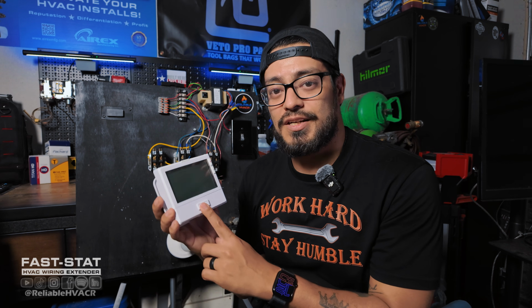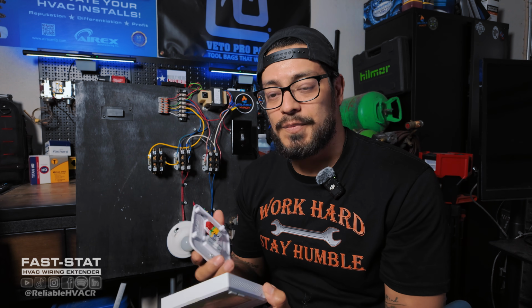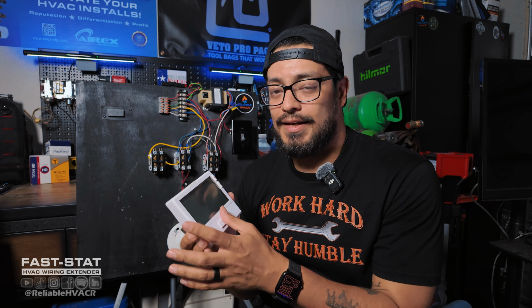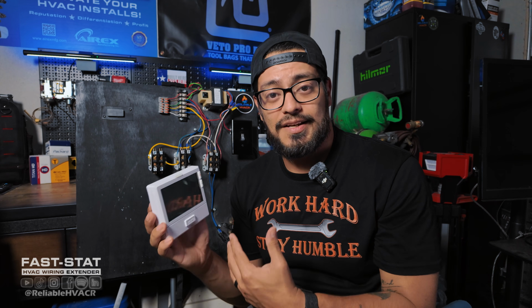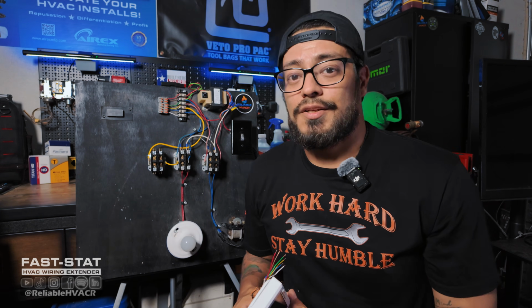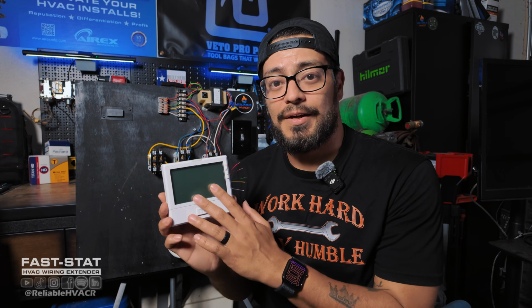So you want to make sure your thermostat is working properly first. So you take that off, check for batteries, check for a common. Typically, any Wi-Fi thermostats, things like that, are going to require a common, not batteries. Then you're going to need to find out why we don't have a display, right? So you lost your 24 volts. Next steps vary in different situations. Obviously, if everything is working properly, you're going to start checking your capacitors, low pressure switches, charge, things like that. There's going to be different things that you need to look at, right? But if you go in there and it's a low voltage issue, it's probably going to be one of two things.